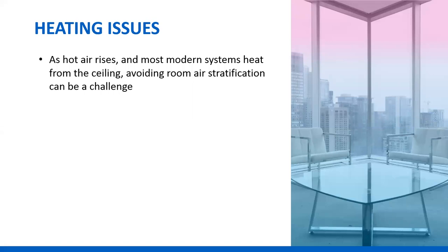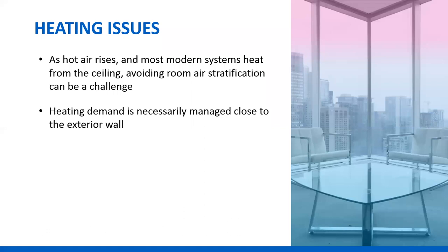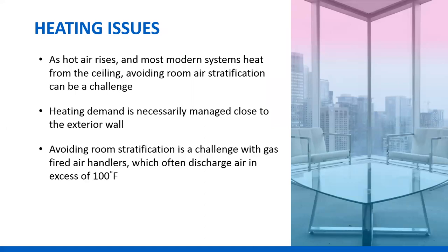The good news is you only really have to manage heating demand right close to the exterior wall. There's a cold sheet of air moving down a window when it's cold outside, and you need to temper it when it falls into the space. Avoiding room stratification is especially challenging with gas-fired rooftops, which may have discharge temperatures in the 120–130 degree range. If you deliver that directly into the room, the room is going to stratify.